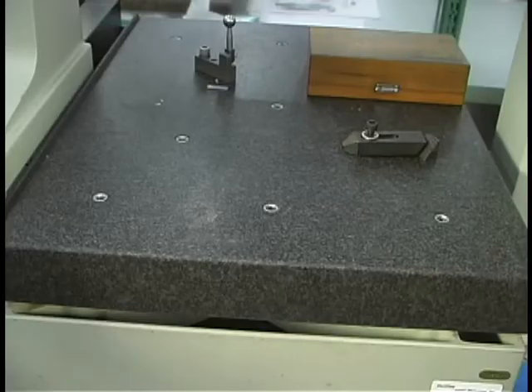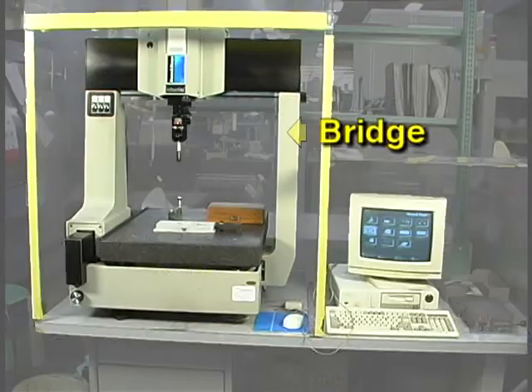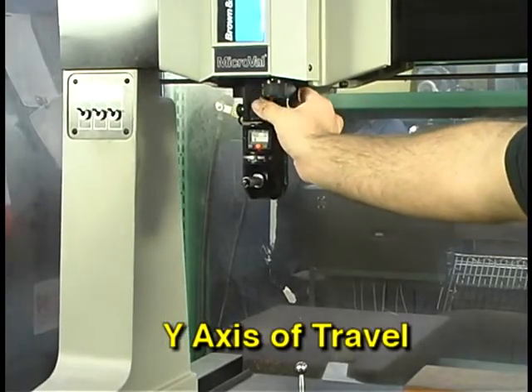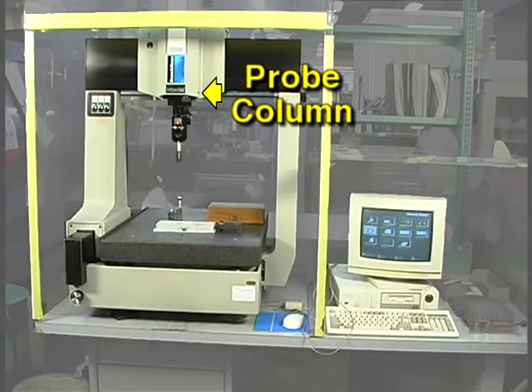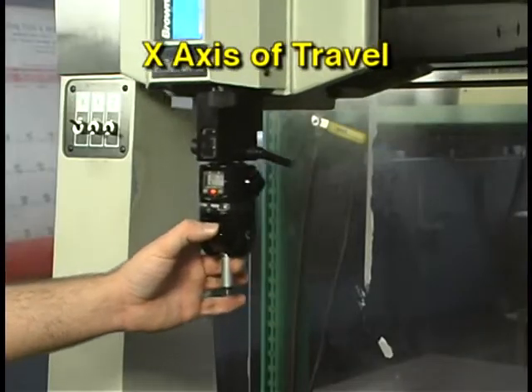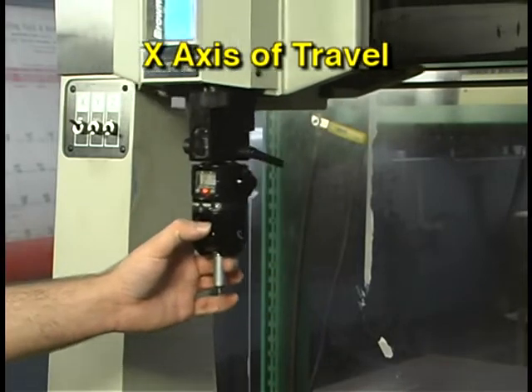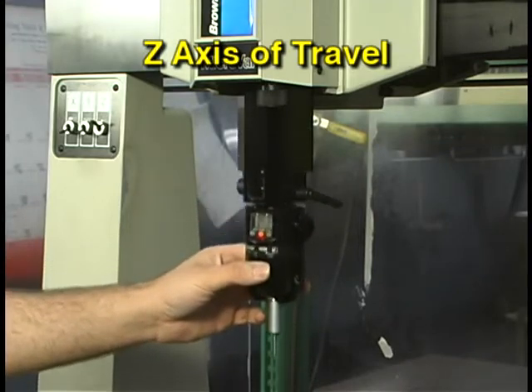Most shop CMMs include a surface plate for mounting workpieces to be measured. Over the surface plate is the bridge. The bridge can move back and forth as the Y axis of travel. Mounted on the bridge is the probe column. Movements of the probe column back and forth across the bridge are movements in the X axis. Movements of the probe column up and down are movements in the Z axis.